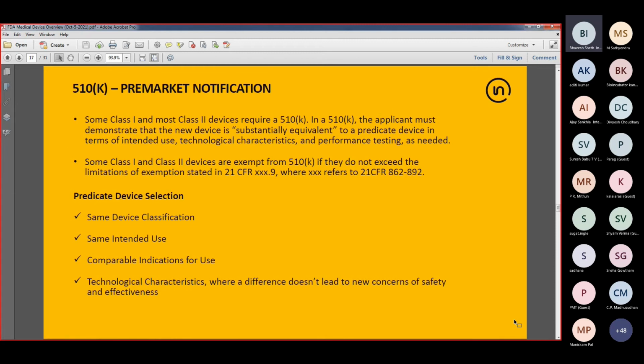We'll talk first about the 510K, and we'll spend a little more time on this topic because there's a good amount of interest in knowing how to find predicate devices. So I'll show some examples. As I mentioned earlier, some class 1 and most class 2 devices will require a 510K. In a 510K submission, it's not sufficient just to show the safety and effectiveness of your product. Basically, if you present your test data and compelling evidence that your product is safe and effective, that alone is not sufficient. You need to demonstrate that your device is also substantially equivalent to a predicate device in terms of its intended use, technological characteristics, and performance aspects.